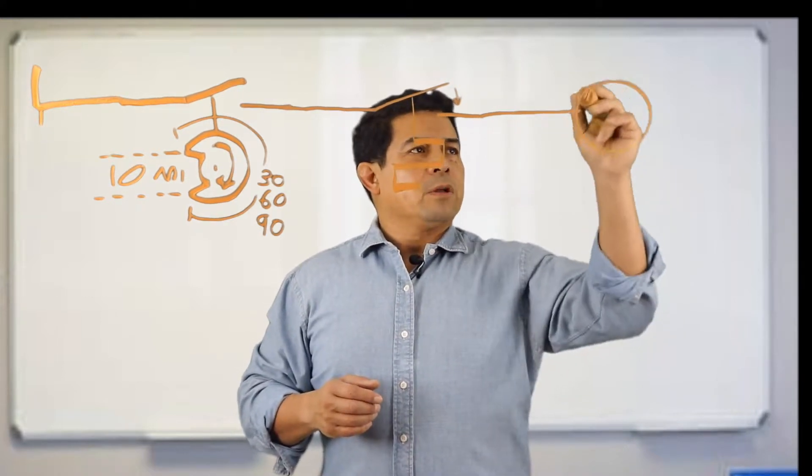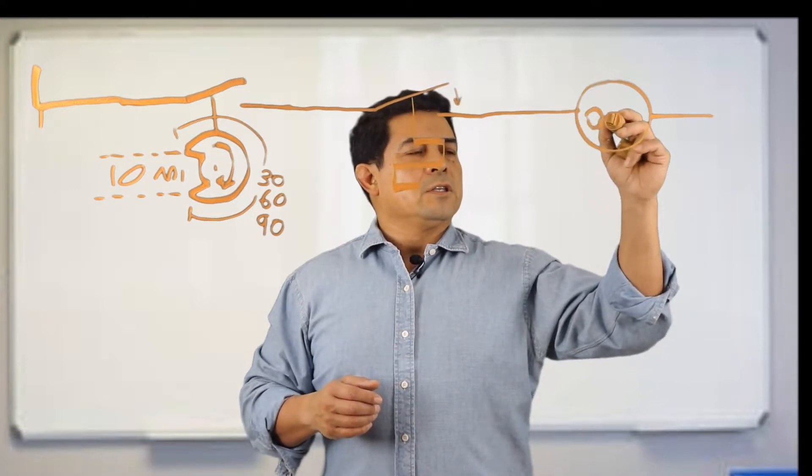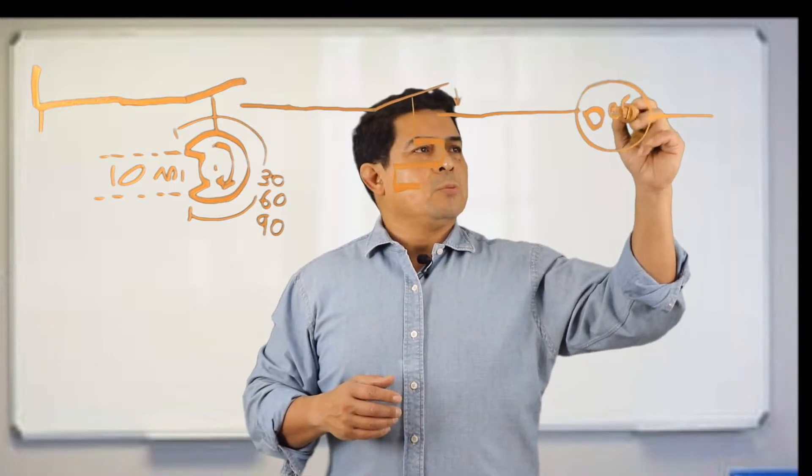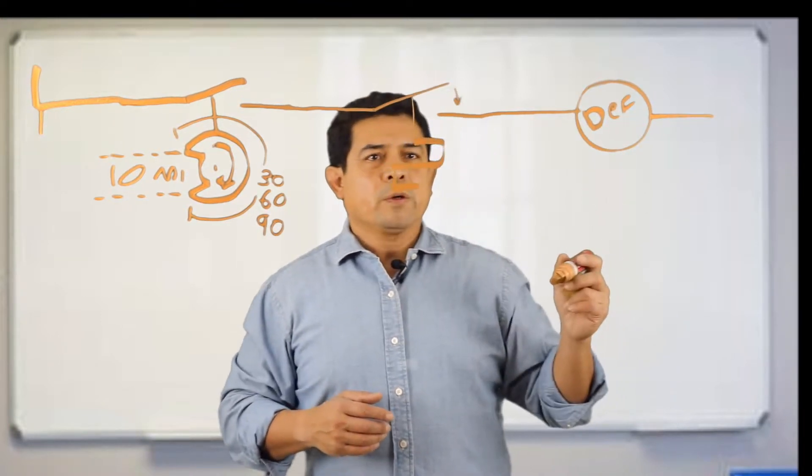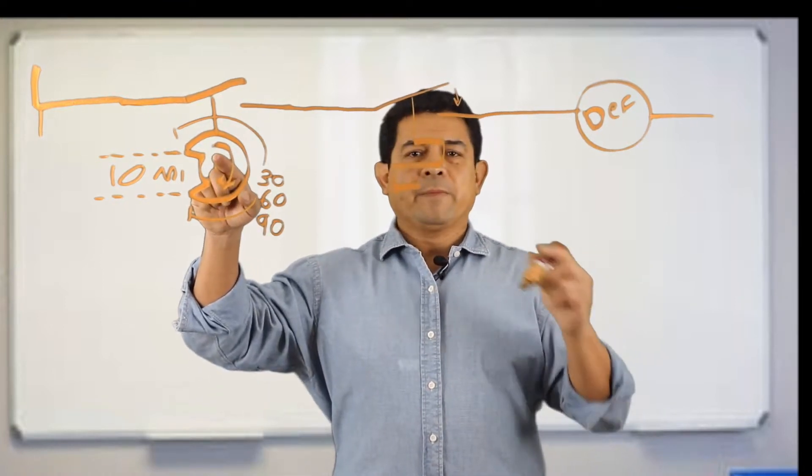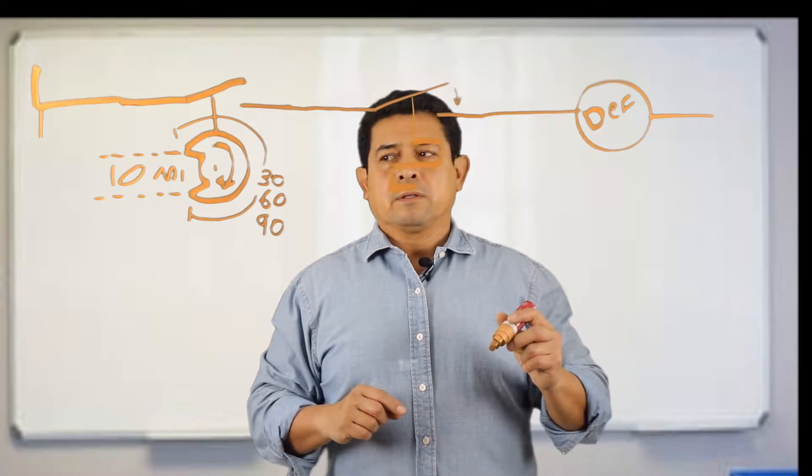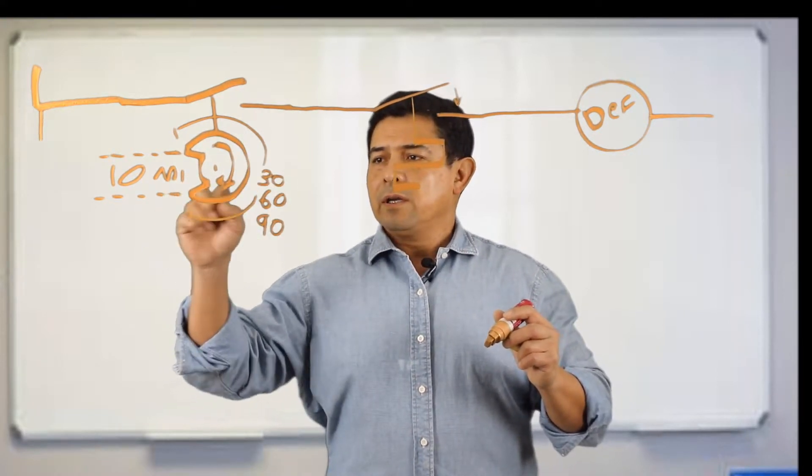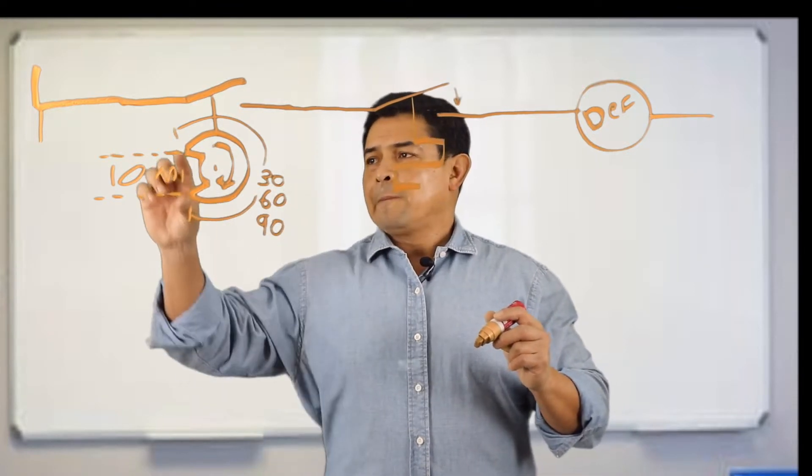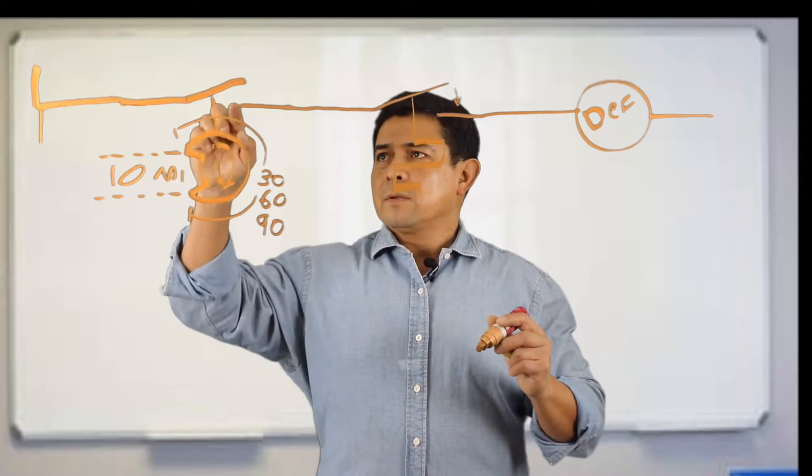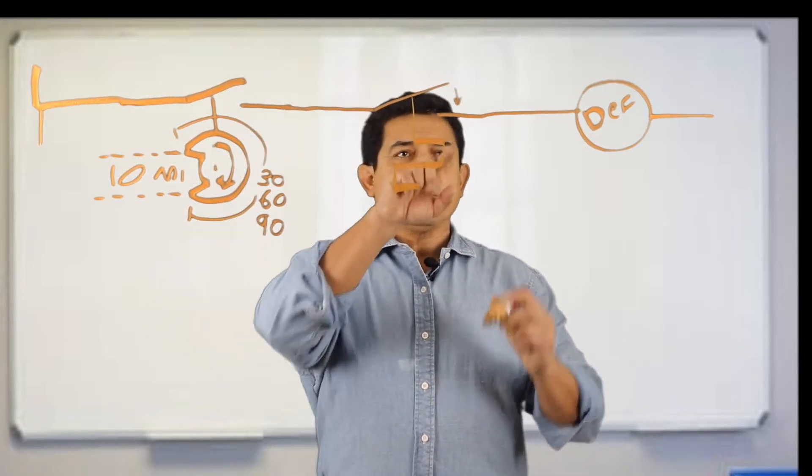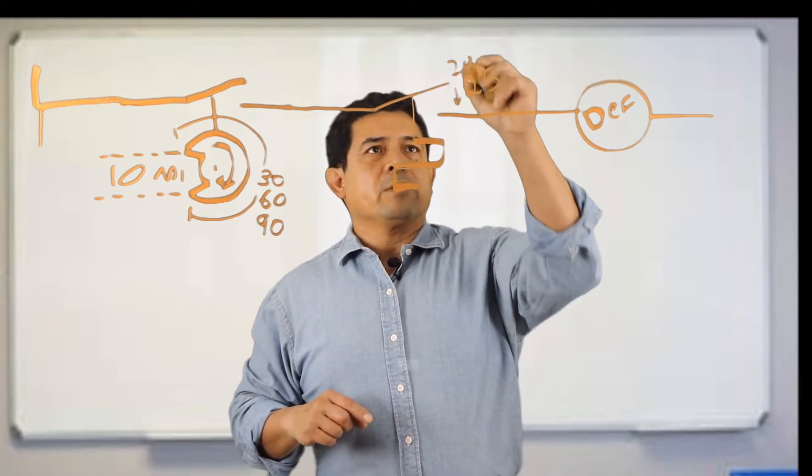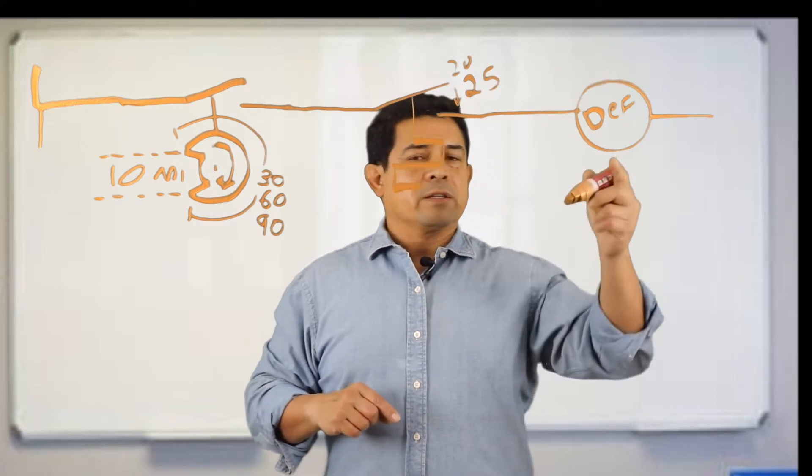This is going to go to your defrost relay or defrost controls. So for it to go into defrost, it's going to be by time and temperature. For this to go all the way around is going to be 30, 60, or 90 minutes. This is the 10 minute time period, so this will be closed for 10 minutes. Once the temperature drops down to 20 or 25, that's going to close, then it's going to go into defrost.